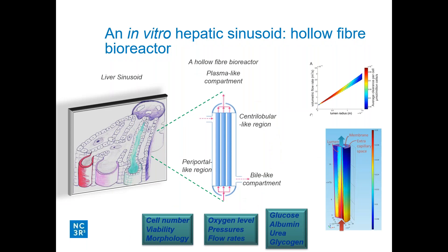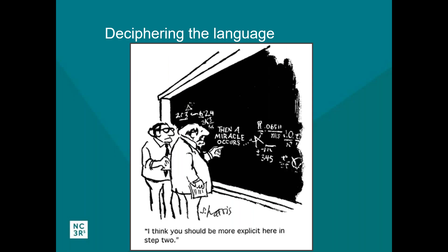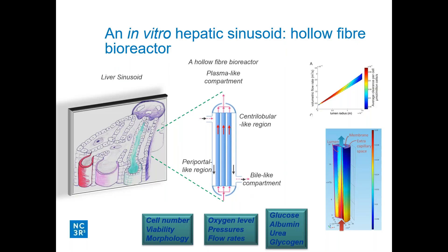The kit they developed is essentially a number of hollow fibers combined into a single bioreactor. Each hollow fiber is lined with hepatic cells, and there's a series of outlets enabling sampling for real-time analysis of metabolites. It's possible to pump fluids and test compounds through the lumen of these hollow fibers and down along the cells, which line the lumens, enabling them to absorb the nutrients, oxygen and compounds — so you can see gradients similar to those in the in vivo sinusoid. This provides a tool that will hopefully be more useful to industry in determining which compounds are likely to be liver toxicants much earlier in preclinical development, removing those compounds from the pipeline before they go into later animal regulatory testing, reducing the need for animals and also the cost to the company.